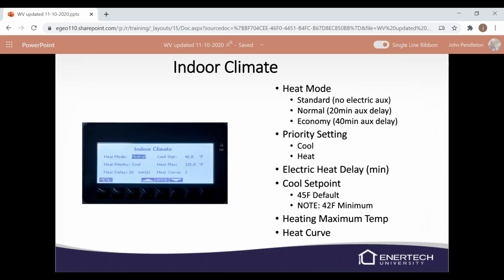On indoor climate, in your heat mode, you can put it on standard, which is no electric auxiliary. You can put it on normal, which is a 20-minute auxiliary delay, or economy, 40-minute auxiliary delay for your auxiliary heat. You can set your priority, whether that be cooling or heating. So if you get a home heating or cooling need, you can decide which one comes first.